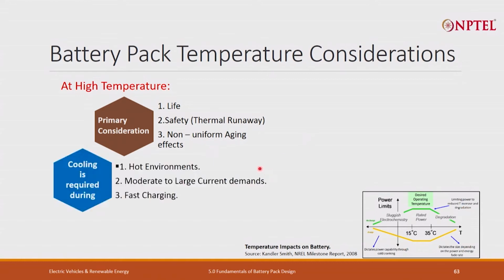Cooling is required in hot environments with moderate to large current demand. Whenever you are taking moderate to large current, heat generation is high - Joule's heating, which we studied during the electrical design, I square R, is very high. So in such cases again we require cooling of the battery pack, even though the ambient condition is 25 or 30 degrees.